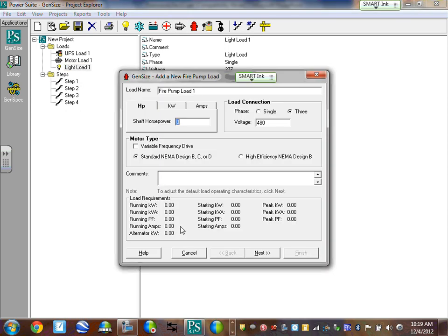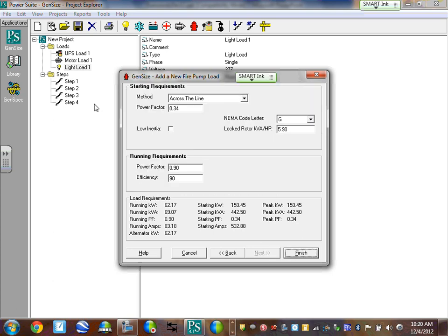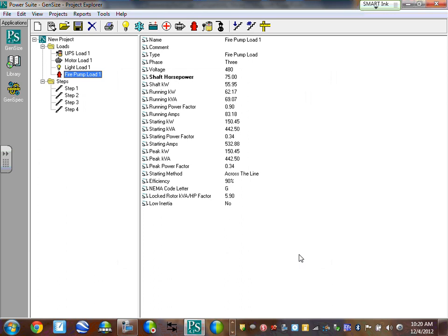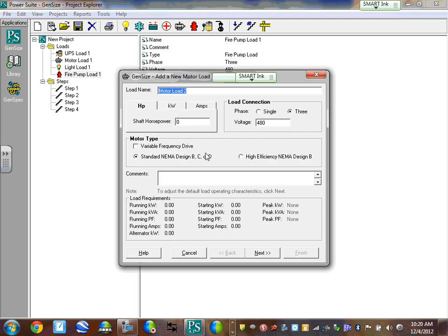And we better try a fire pump too. We've got a bigger building, so we're going to have a 75 horsepower fire pump at 480. Okay. There's an option for VFDs there. I don't know if the Cummins program is intuitive on that. We'll find out. On the fire pump, you have a 15% maximum voltage dip requirement. And we're going to see if they take that into account. And we better throw on a chiller here too.